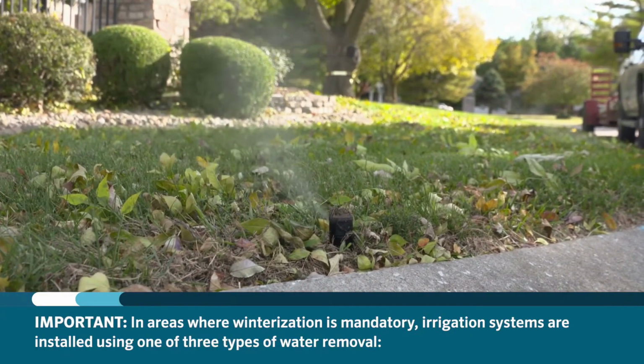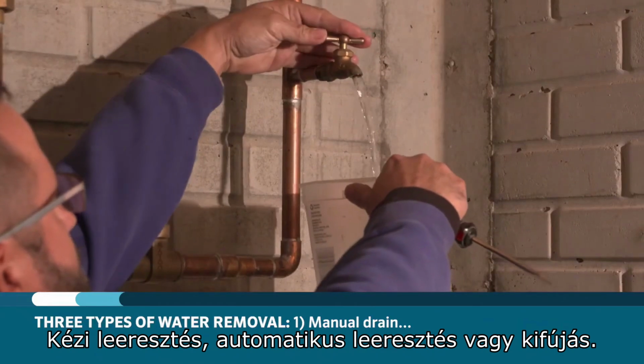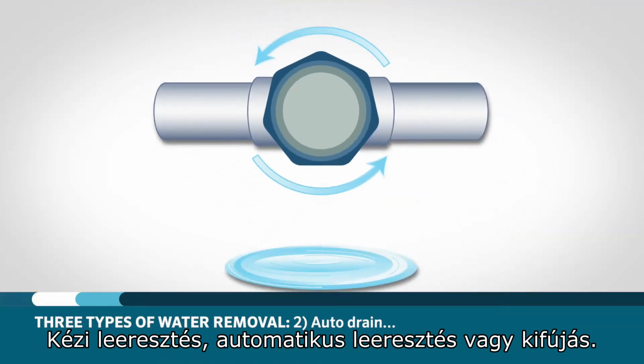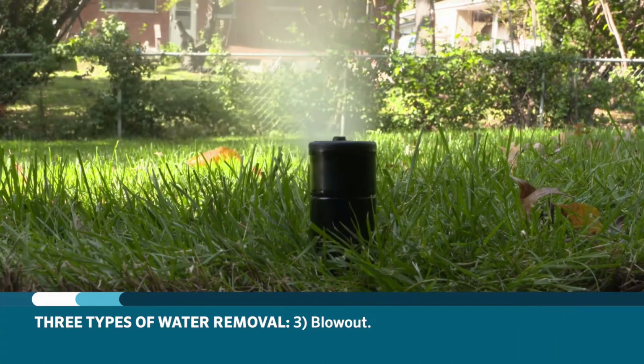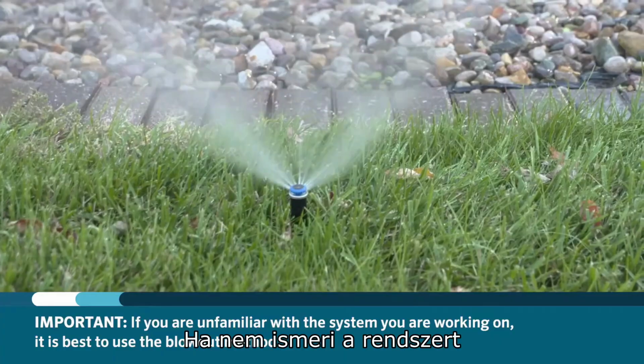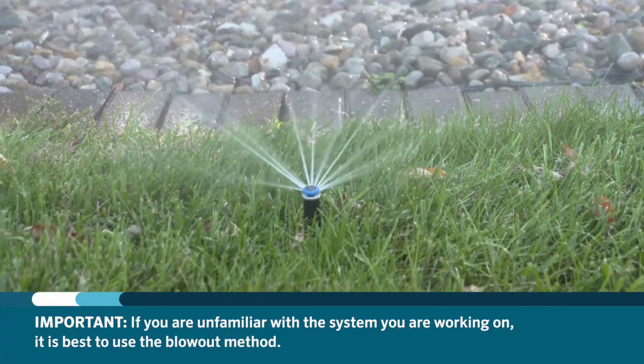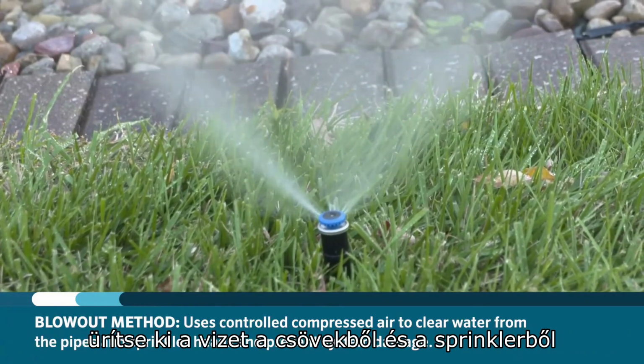water removal: manual drain, auto drain, or blowout. If you're unfamiliar with the system that you're working on, it's best to use the blowout method. The blowout method uses controlled compressed air to clear out water in the pipes and sprinkler heads to prevent damage to the system.